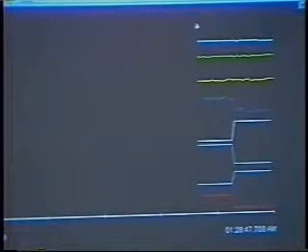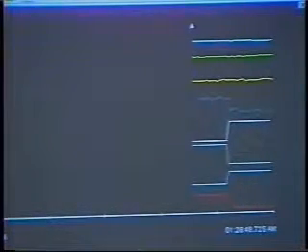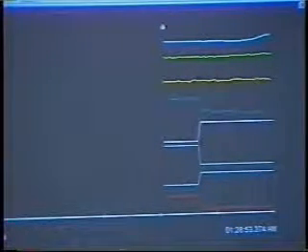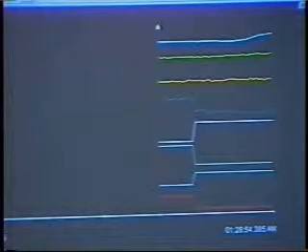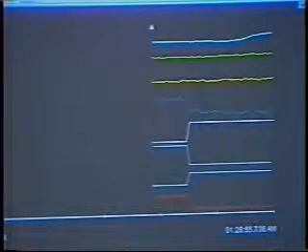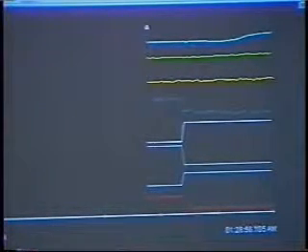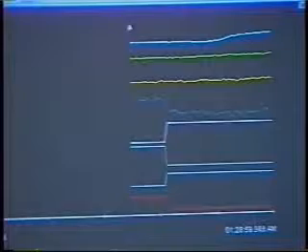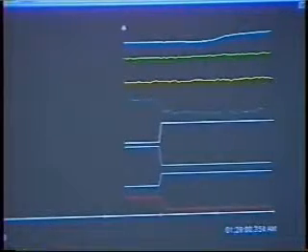The data logger stepped through the temperature and voltage inputs and displayed them in a strip chart mode. As you can see, there was a temperature rise in the transformer as the load varied, but it was well within specifications. Similarly, output regulation was good under all load and line voltage conditions.